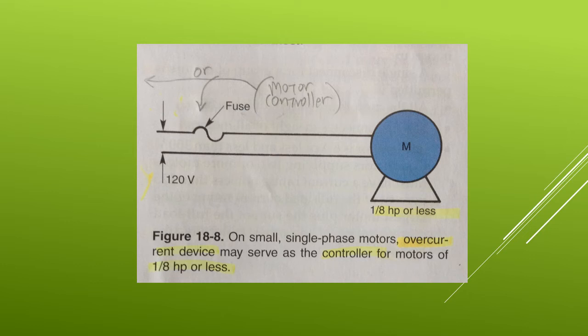Control methods. On small single-phase motors, the OCPD may serve as the controller for motors that are rated not more than 1/8 horsepower, stationary, and normally left running. For this, see figure 18-8. A good example would be a clock motor.